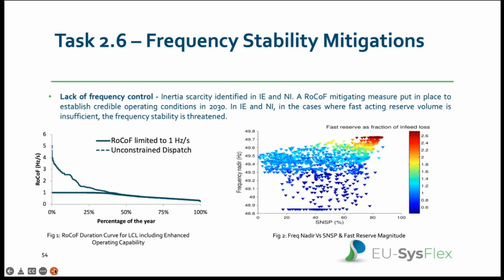Therefore, a mitigation measure was included within simulations where we introduced a 1 Hertz rate-of-change-of-frequency constraint into the scheduling and dispatch simulations in Plexos. There are two ways we can satisfy this limit: one, by committing more conventional generation to increase the system kinetic energy, or two, by reducing the largest single infeed.